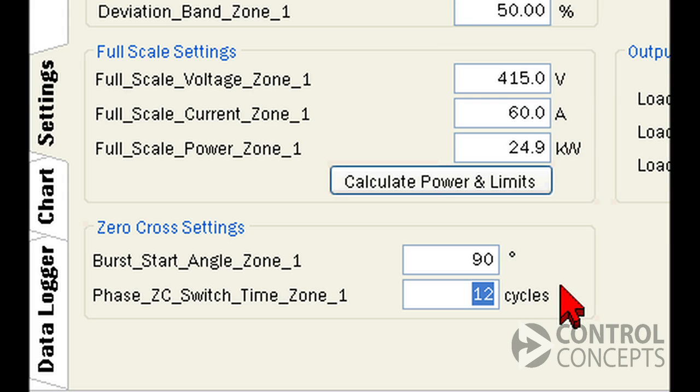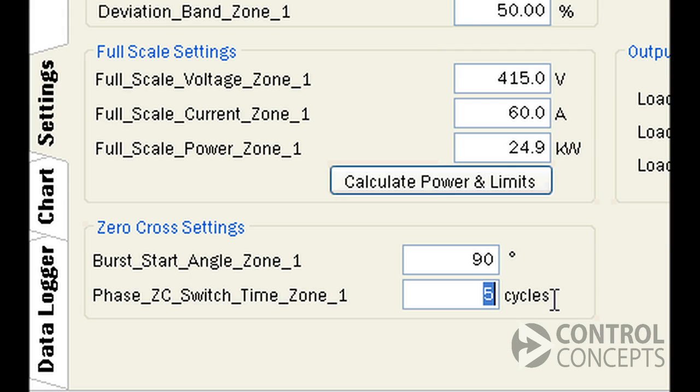This next setting is for the zero cross phase angle start firing mode. It determines how many phase angle cycles will set up a magnetic field in a transformer. The default setting is 12, and a lower number means an improved power factor, so test with your load to select the best setting.